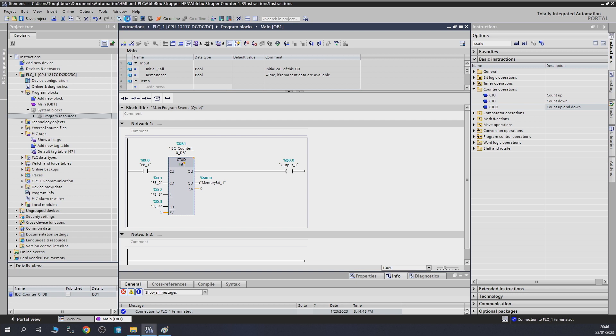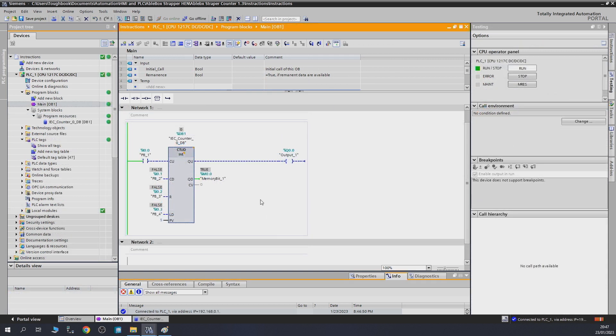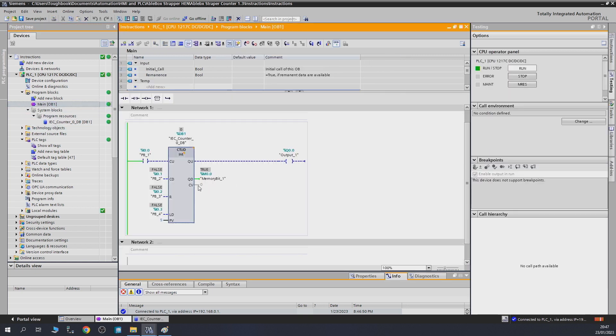Here we go. As always, don't forget you can query any of these data in that specific counter's data blocks. All that data is accessible within their respective data blocks. As you can see, my memory bit, my down count, is set to true because the value is at zero. Every time the value reaches zero, the down count will be on because you've reached the zero point.